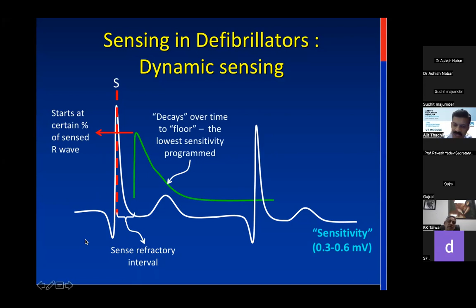And then it gradually decays to the program sensitivity. The program sensitivity here is 0.3 to 0.6. When we say 0.3 to 0.6, that means this number is somewhere between 0.3 and 0.6. If you were to keep 0.3 to 0.6 here, you would sense this T wave. This decay allows us to maintain the low sensitivity after the T wave has elapsed, but at the same time not sense the T wave. So this is how an ICD senses.